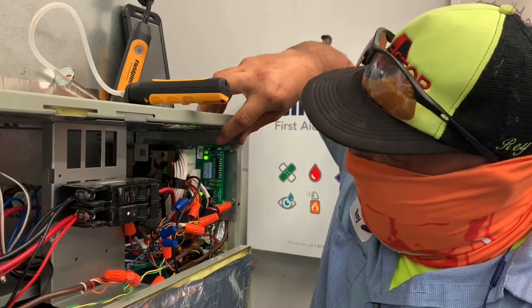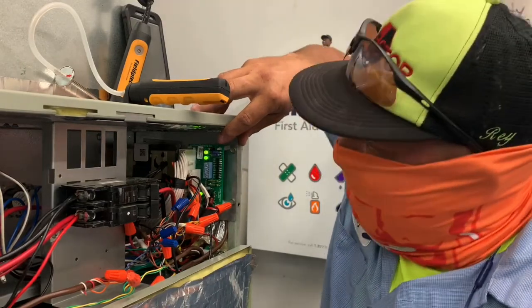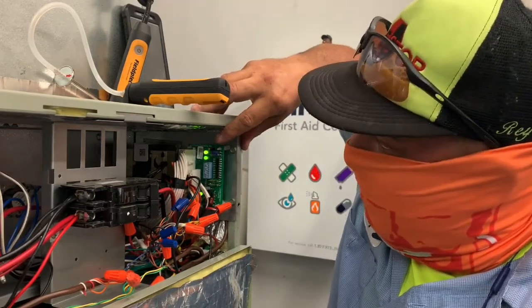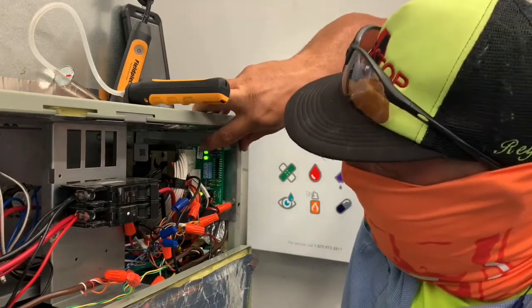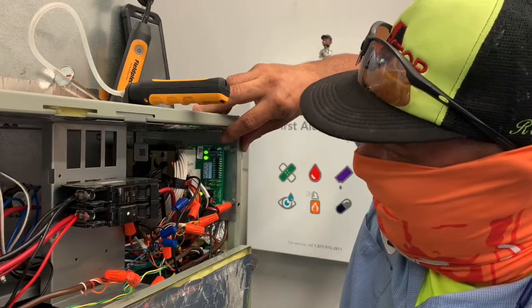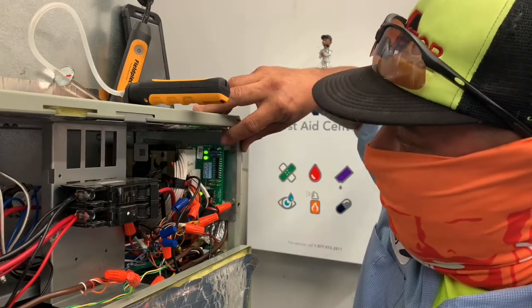For example here — I think I might have missed the count itself. I'm trying to explain it, so we'll wait until it resets itself. But again, this top light right here — once you count the flashes, you'll know how many CFMs this blower is producing.